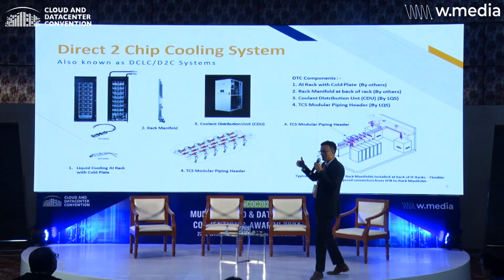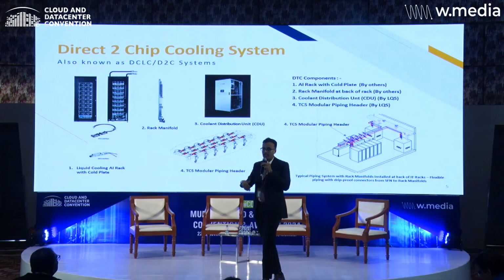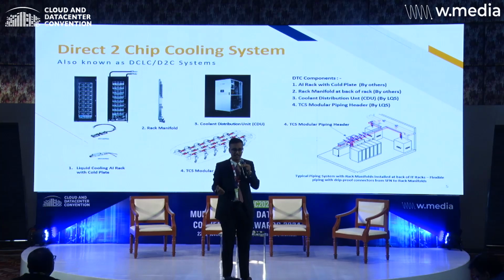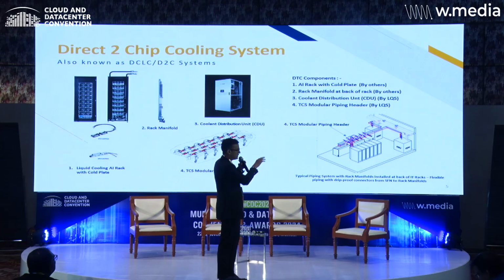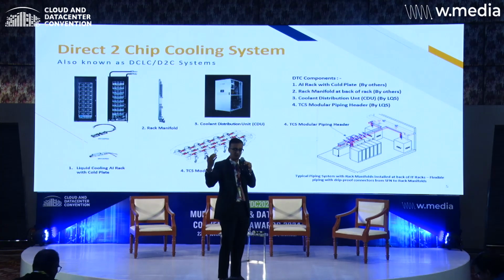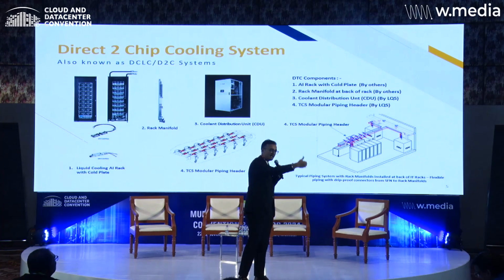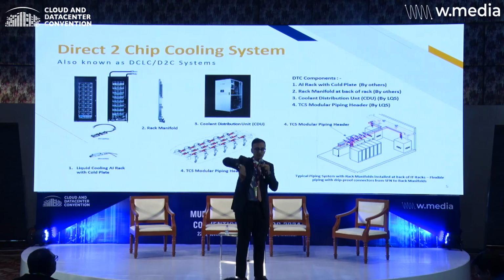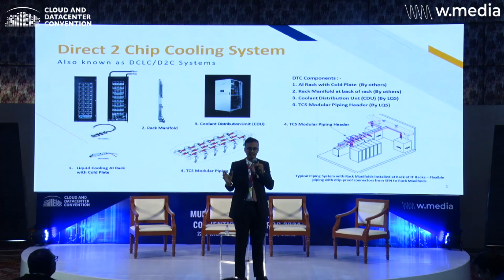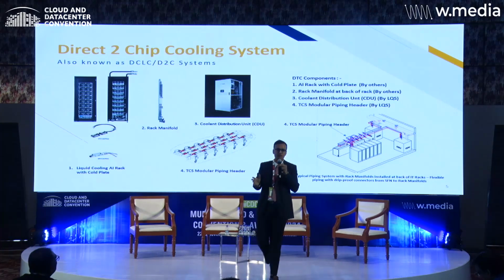So you will have an N+1 redundant configuration or an N+N redundant configuration, based on your design. But basically, what the CDU does is transport the coolant to the chip and get the hot coolant back, and in the CDU there is a heat transfer with the facility water. That's the basic CDU functionality. In this case, you're getting a PUE of approximately 1.25, 1.26, which is already a 30% reduction compared to today's PUE in India. So it's a massive PUE saving, plus you're already computing 100 kilowatts plus in one single rack.